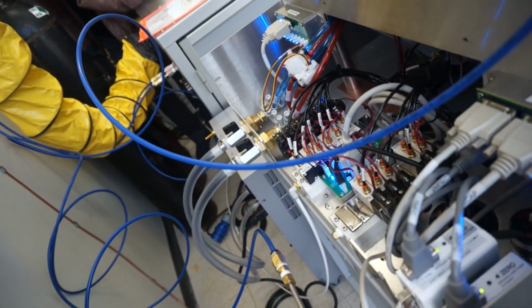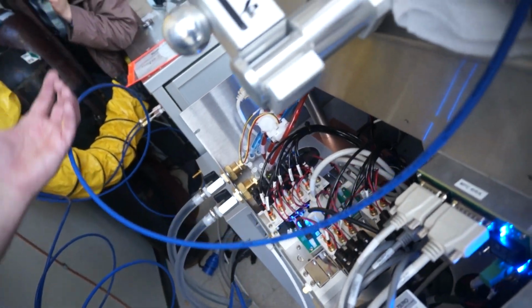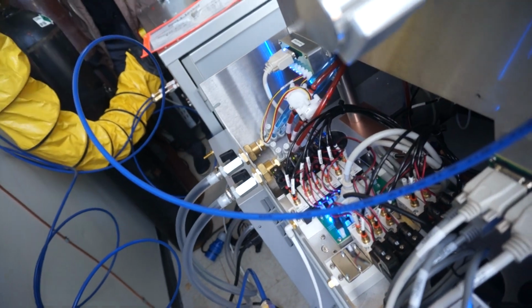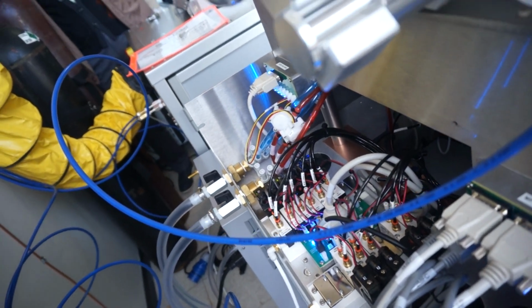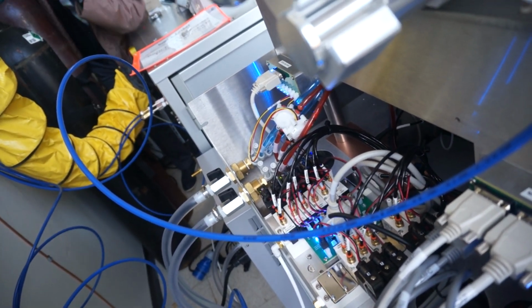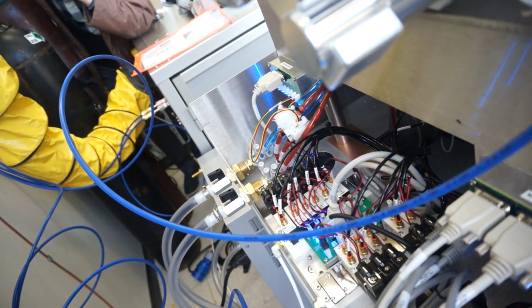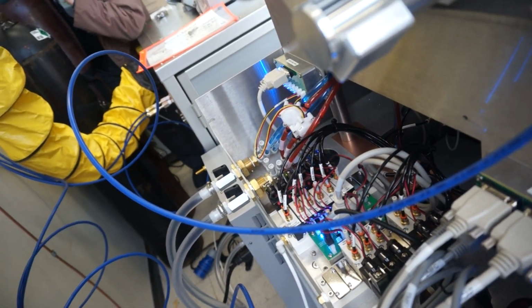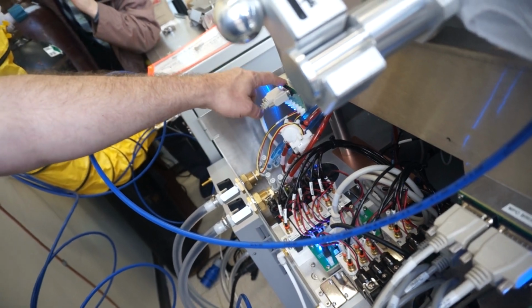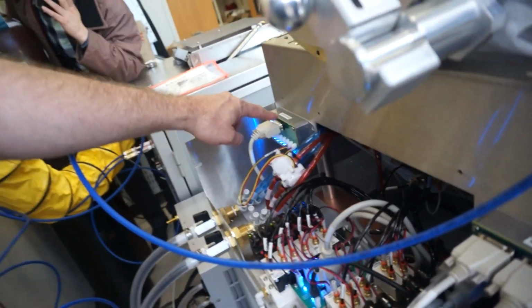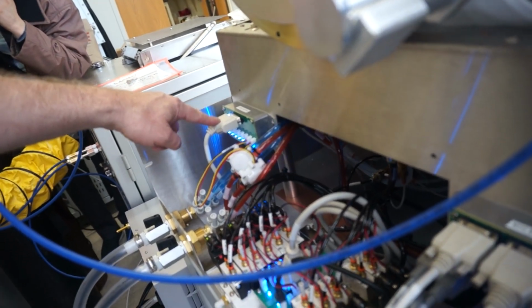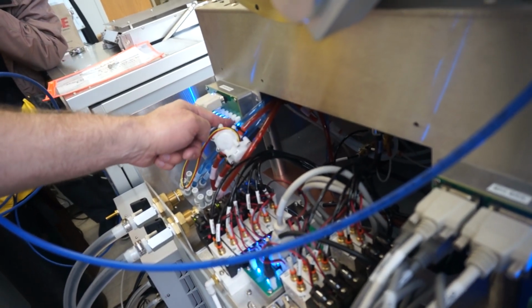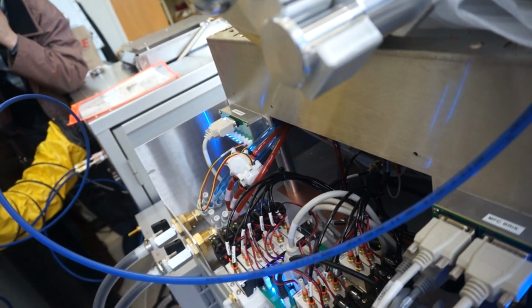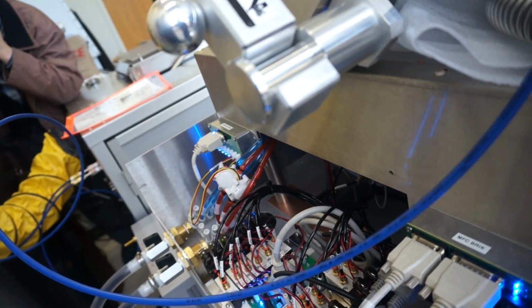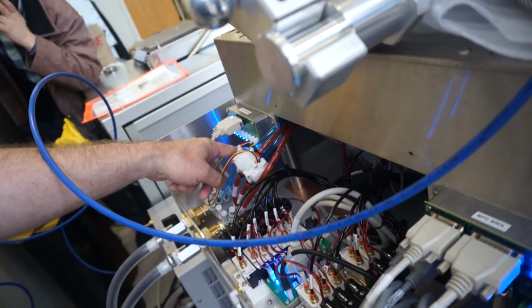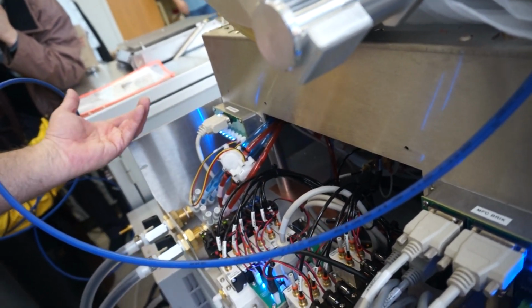So in the front of our tool, we have what we call a Rigel controller. The output of the Rigel has basically D-sub connectors that we use pre-molded cables that we plug from the output of the Rigel to these bricks. And so this is the cooling brick. So this is an input brick. Each of these flow switches go to here, and if we have the required flow set point, we get a LED which illuminates saying that is satisfied.